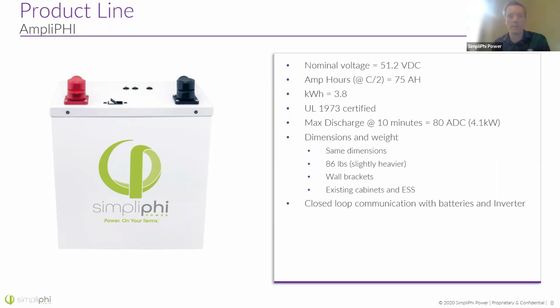This is a UL 1973 certified battery, as are all of ours. On max discharge, that screen number is actually lower than what it's capable of. This battery is capable of surging to 100 amps DC. In other words, a single one of these batteries can put out 4.1 kilowatts for 10 minutes.